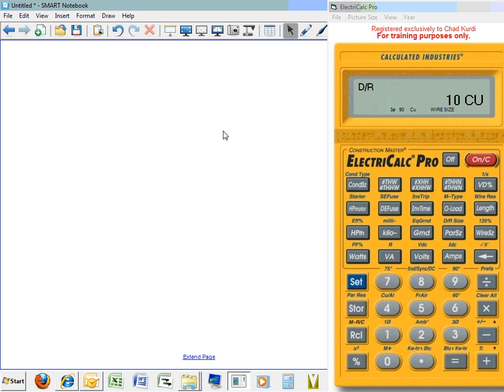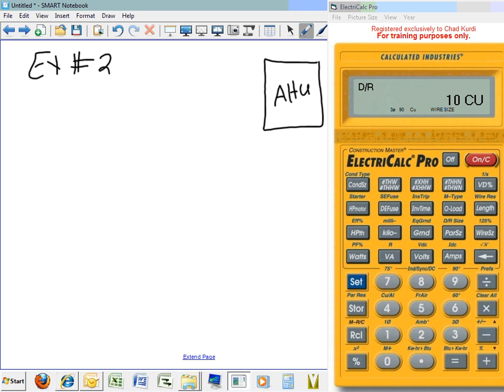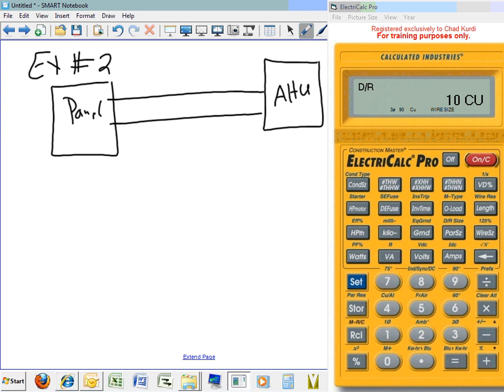Now let's take one more example, guys, about the rating, both temperature and ampacity, and that will be example number 2. I have an air handling unit. You guys have a problem with that? Air handling unit, and I have my panel. From my air handling unit to my panel, I'm paralleling conductors. You don't come from the side of the panel, you come from the top. Let's do it the right way. I hate doing it coming from the side of the panel.